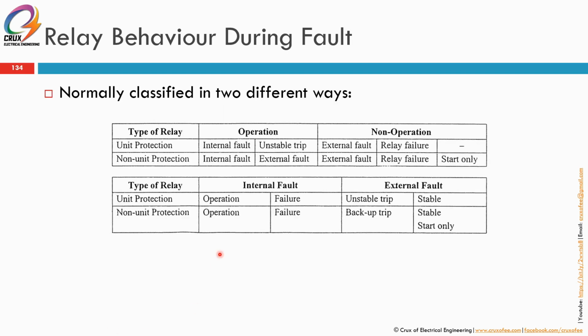So relay behavior during fault is normally classified in two different ways. Unit protection will operate for an internal fault, but for an external fault, it will not operate. Non-unit protection will operate for both internal and external faults. So for type of relay: unit protection, internal fault, operation; external fault, stable. Same goes for non-unit protection: for an external fault, it will become a backup trip. This is if it's a backup protection to the downstream breaker.